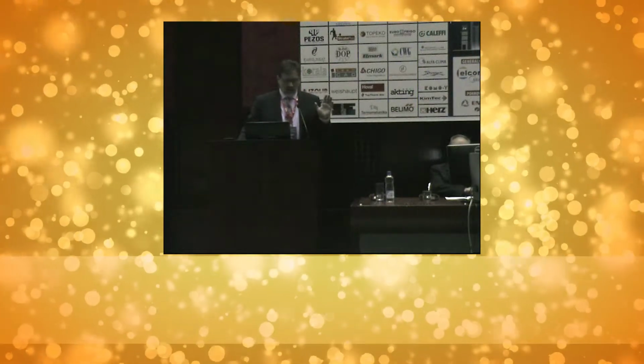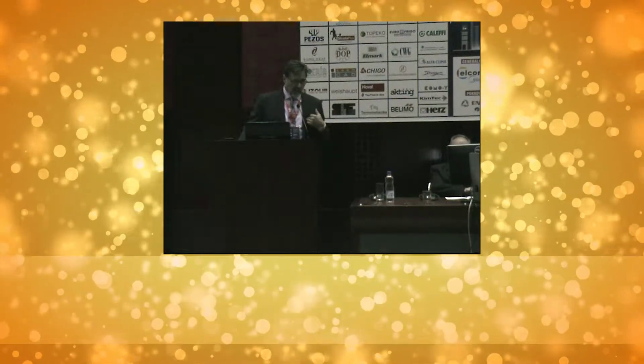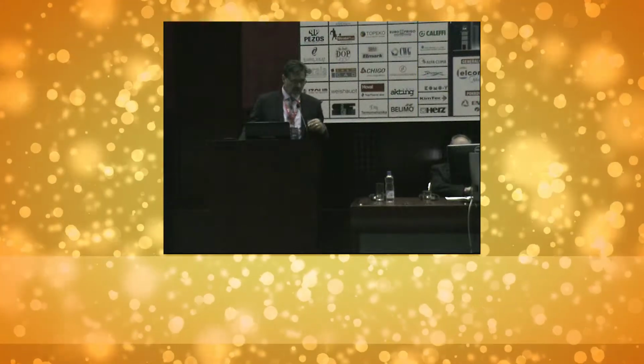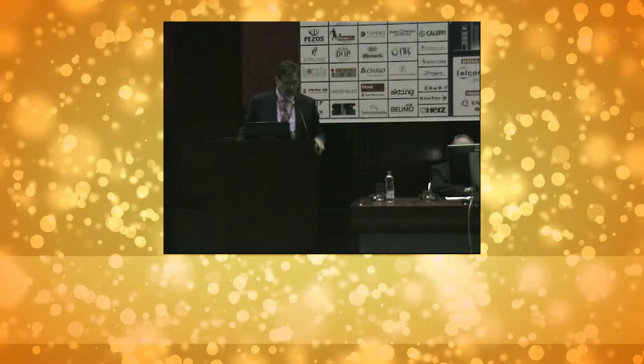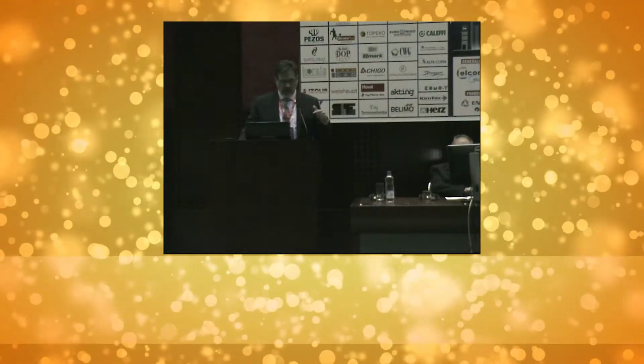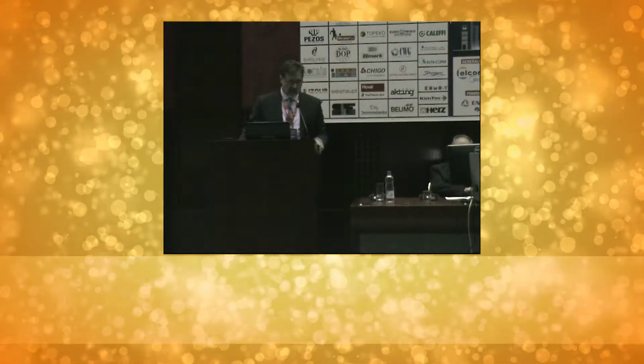2,000 is okay, don't exceed it, but when I have to design something, I stick with 1,500 because of future developments. You never know if your load calculation will really meet the need. Somebody's going to change something, as in the previous presentation, so you give yourself a little reserve. So my recommendation would be 1,500, with 2,000 as the maximum.